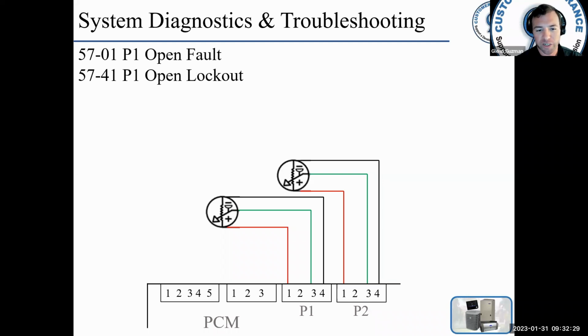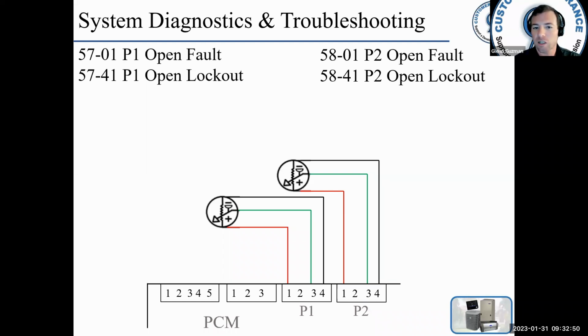So we can get a couple faults here. Each transducer is going to have three wires: a ground, which is black, power, which is red, and a signal wire, which is green. Pressure in the system is converted to an electrical signal, and the board and software can interpret that signal.